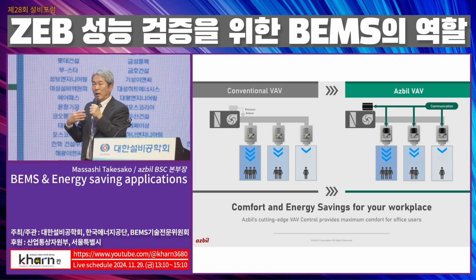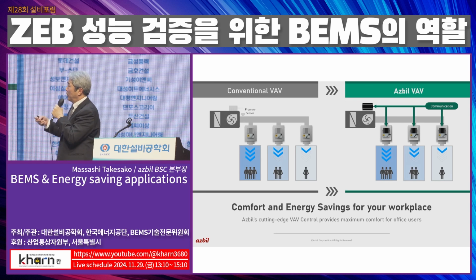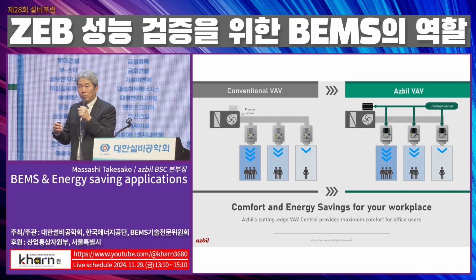That's why what I would like to say is, to consider energy saving, we should not only focus on one facility, like only the fan or only the pump. We have to think about related facilities like the VAV or control valve, and in the case of a chiller, we also need to think about the cooling towers, condenser pump, and chilled water pump. All these facilities have to be considered in order to achieve the best operating point.